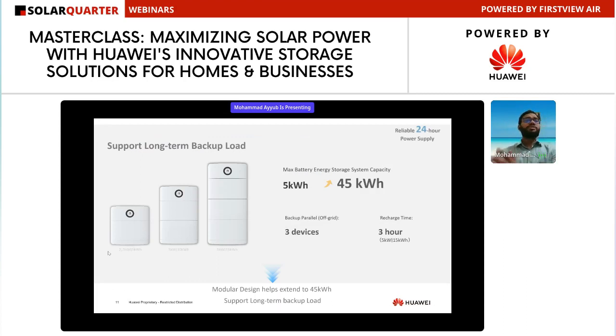Now, let me take the pointer. On the left side, the upper one is called the power module, which is a 5 kilowatt capacity, and the lower one is the battery module, which is 5 kilowatt hour. Our system supports the 0.5C application, which is a 2-hour backup. Only in the condition where we have one power module and one energy module do we limit the power to 2.5 so that the C rate is 0.5C.